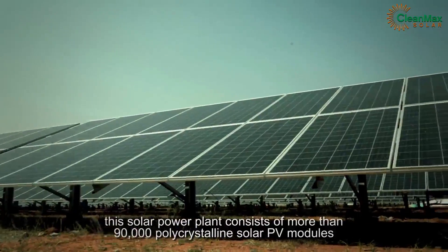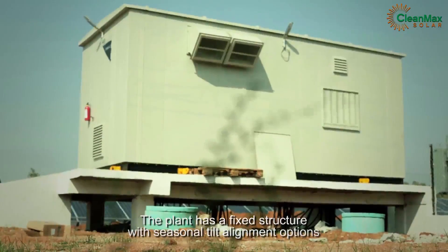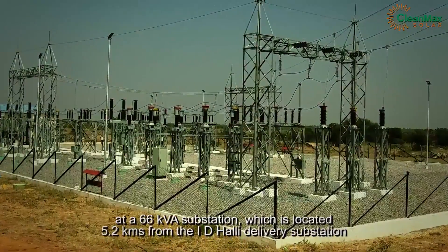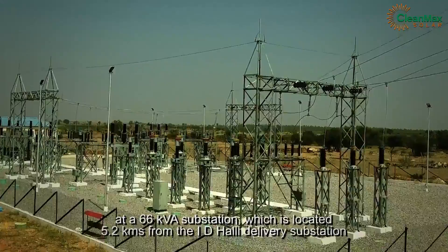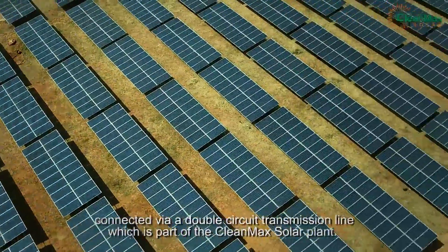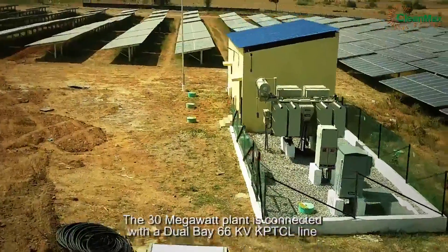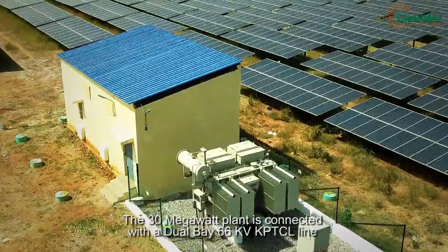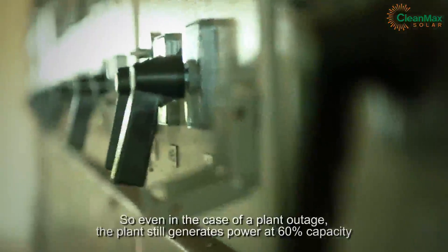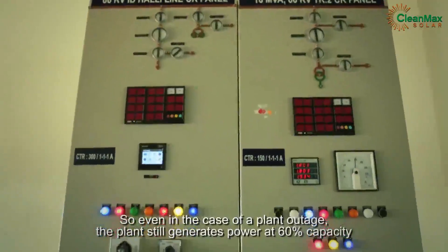Spread across a total area of 170 acres, this solar power plant consists of more than 90,000 polycrystalline solar PV modules. The plant has a fixed structure with seasonal tilt alignment options. The solar power is injected into the main grid at a 66 kV substation located 5.2 kilometers from the I D Halli delivery substation, connected via a double circuit transmission line. The 30 megawatt plant is connected with a dual bay 66 kV KPTCL line with a 16 MVA standby transformer on each bay, so even in the case of a plant outage, the plant still generates power at 60 percent capacity, maintaining better redundancy.